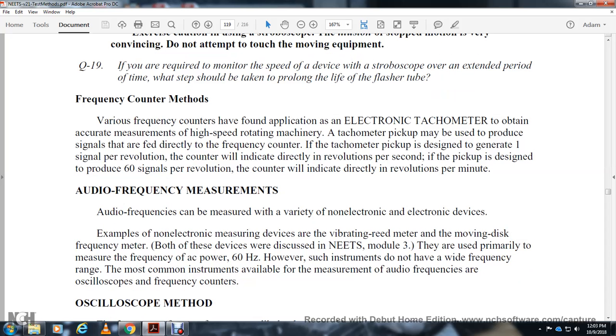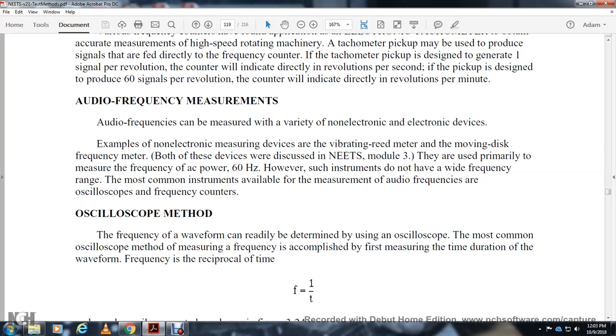Audio frequency measurement. The audio frequency can be measured with a variety of non-electrical and electronic devices. For example, the non-electrical measuring devices are the vibrating reed meter and the moving disc frequency meter. Both of these devices are discussed in NEETS module 3. They are used primarily to measure the frequency of AC power at 60 Hz. However, such instruments do not have a wide frequency range. The most common instruments available to measure audio frequencies are oscilloscopes and frequency counters.